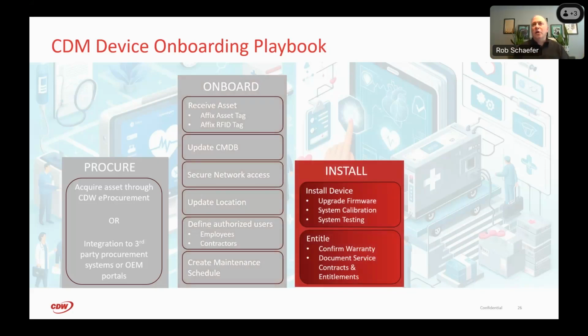Next is the install phase, where we ensure the device has the most current firmware, define the backup procedures, calibrate the device if appropriate, and perform system testing to make sure the device is available and properly functioning. We ensure authorized resources are properly trained. Finally, we confirm the entitlements, including warranties and the service contracts, are in place.